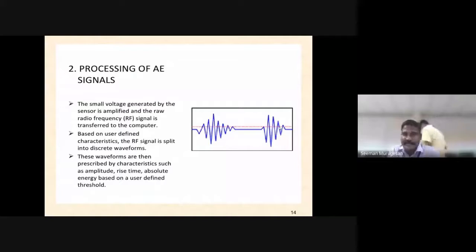Actually, it's a piezoelectric sensor. I already know what the piezoelectric effect is: mechanical energy is converted into electrical energy, or electrical energy is converted into mechanical energy, vice versa. So the small movement of the molecules due to those waves will be sensed by the sensor. These sensed mechanical waves will be converted into an electrical signal, and based on user-defined characteristics, the raw frequency signal is split into discrete waveforms.